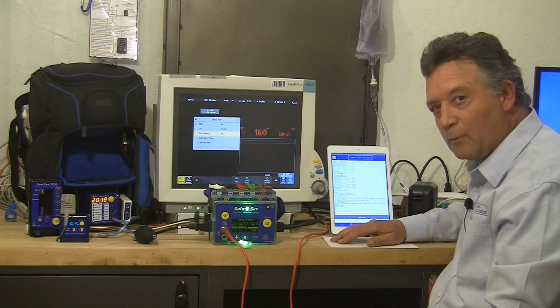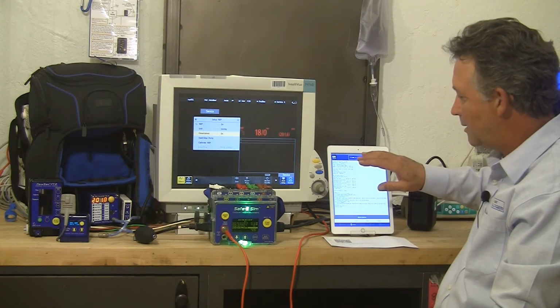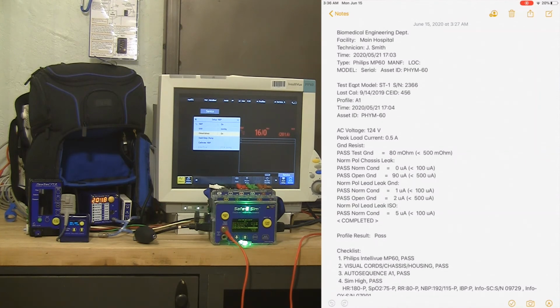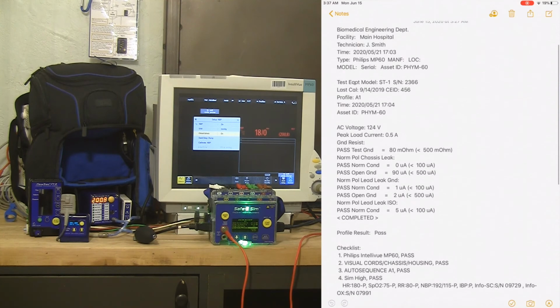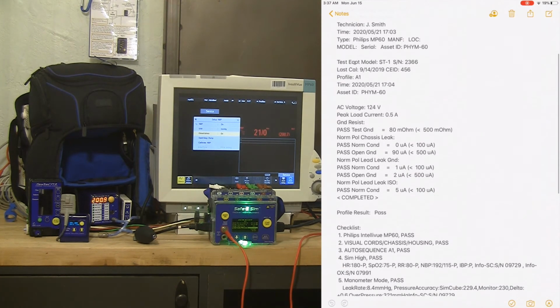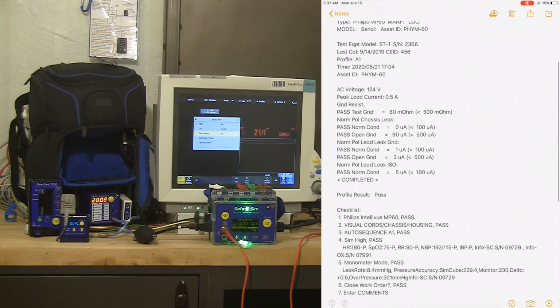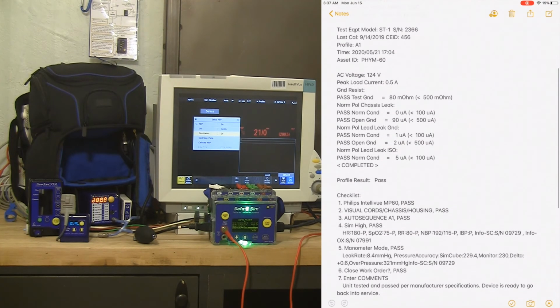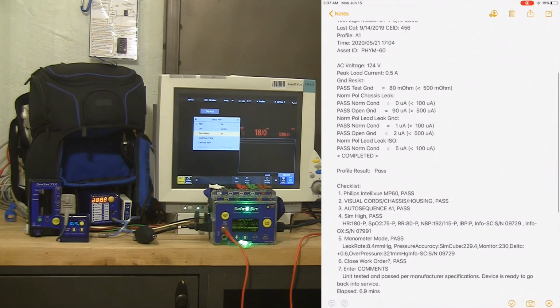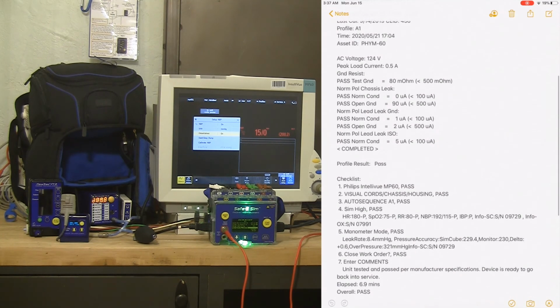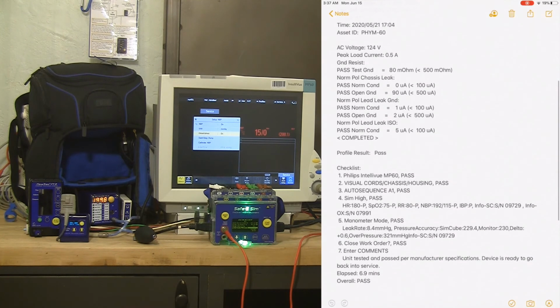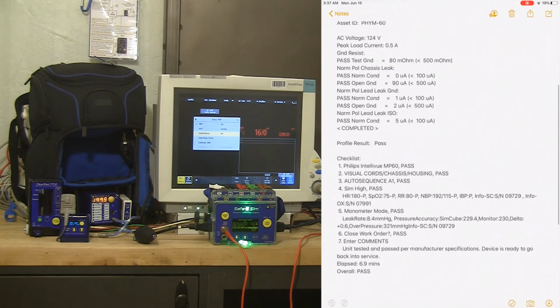The electronic report that we just captured has a ton of detail in it that we built into that report as we went through all of those test steps. And it's worth noting that you've got everything from the technician name, the facility name, the time and date, the device type, the model and serial number of the device we tested with that barcode scan, the test equipment, model and serial number, and CAL information from the test instruments that we're communicating with via Bluetooth, the electrical safety testing in detail. We've got each test that was performed, what limit was used, and the measurement that was taken.